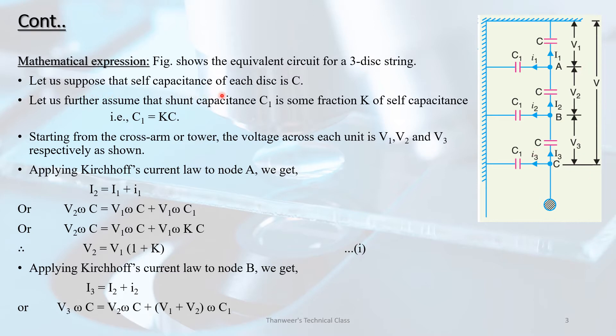Let us suppose the self-capacitance of each disk is C. Let us assume that the shunt capacitance C1 is some fraction K of self-capacitance, so C1 equals K times C. The voltage across each unit is V1, V2, V3 respectively as shown in the equivalent circuit with three discs.